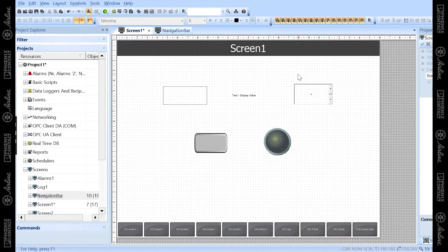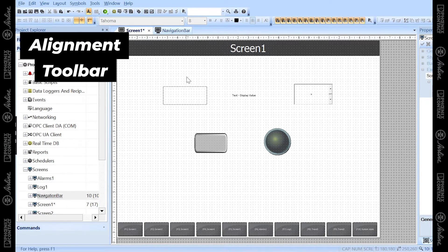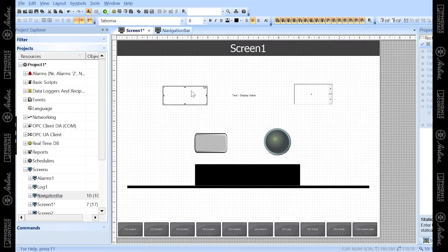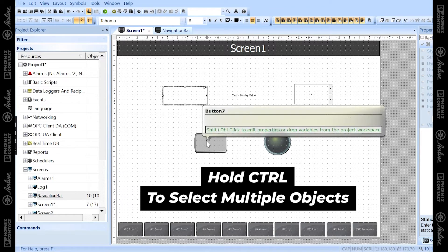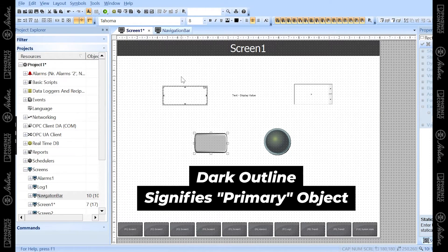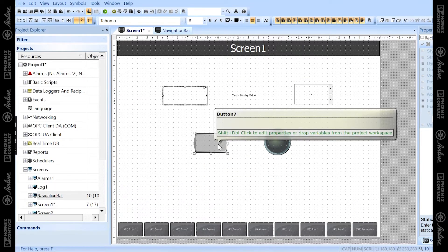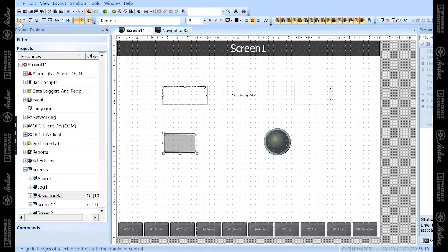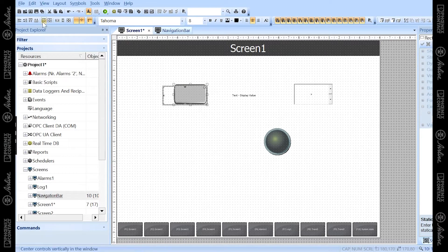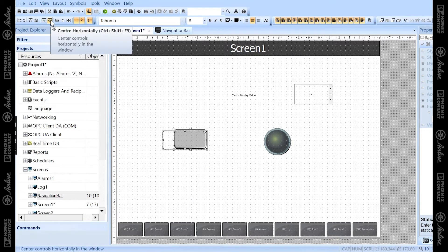Now we're going to move on to how to use the toolbars at the top of the environment, which are crucial to developing your screens, aligning your objects, and editing those objects. The first toolbar is the alignment toolbar. If you start selecting objects and then hold Ctrl on your keyboard and select another object, you'll notice a darker outline on the second object, making it the primary object you're aligning with. For instance, clicking align left will align the push button to the left of that primary object.